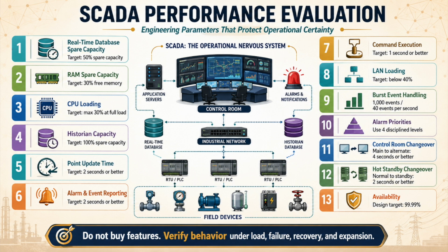A SCADA system does not fail only when servers crash. That is the visible failure, the easy failure, the failure everyone can point to. But the more dangerous failure happens quietly, when operator screens update late during process upsets, when alarms arrive out of sequence, when historians lose resolution, when redundancy transfers slowly, when communication recovery floods the system, and when future expansion exposes that the architecture was designed too close to its limit.